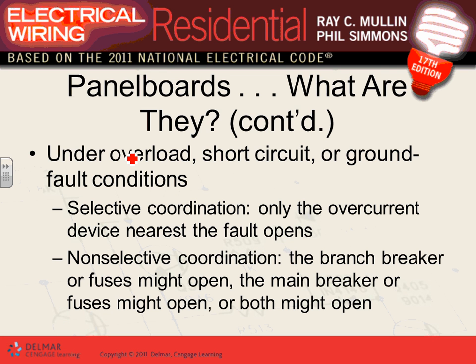Selective coordination versus non-selective coordination: if there's a short circuit in one of these lights above your head, you'd want only that circuit breaker to trip — not the main for the whole building. If only the nearest circuit breaker trips, that's selective coordination. Non-selective coordination is a race — multiple circuit breakers may trip simultaneously.